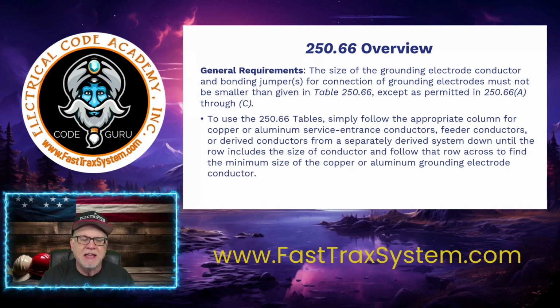But we'll go on and read the information, and then we'll use this to kind of dig deeper into the discussion. So 250.66, general requirements. The size of the grounding electrode conductor and bonding jumpers for connections to grounding electrodes must not be smaller than given in table 250.66. So that is the table that, based on the size of the ungrounded conductors, or based on the equivalent area of paralleled ungrounded conductors.